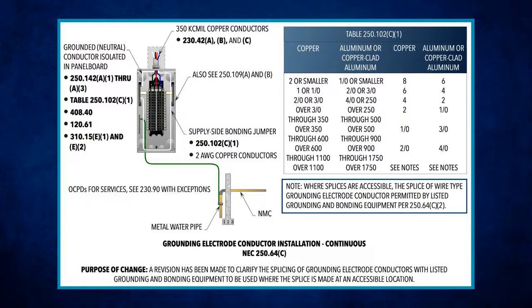Okay, so they got in and they looked at your permitted methods. Of course, you can do splicing of your grounding electrode conductors, or wire type, and that's permitted to be done by an irreversible compression type connector. Then they added 3 here, basically. You still have your sections of bus bar that are connected together to form your grounding electrode conductors. You still have that, but number 2, what they added is where splices are made at accessible locations. Then you can have a splice of your wire type grounding electrode conductors, but it has to be done by a method where you have listed grounding and bonding of that equipment.